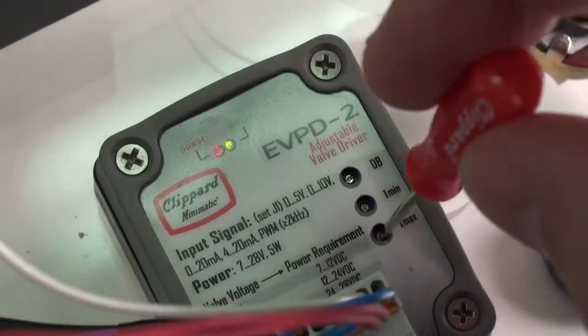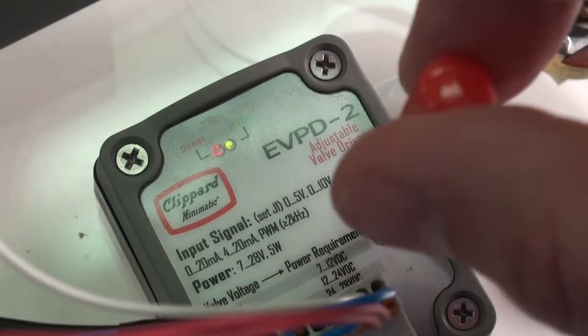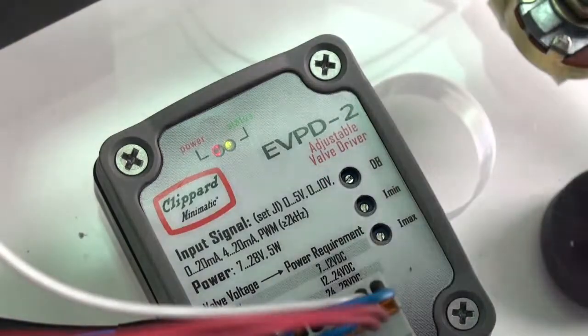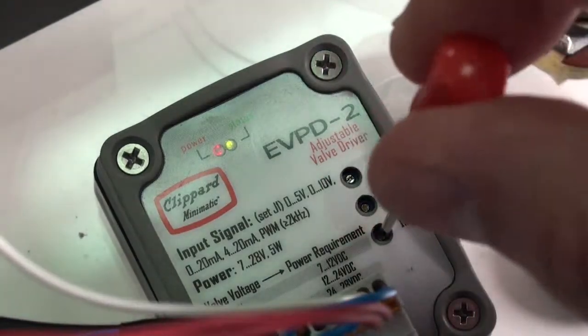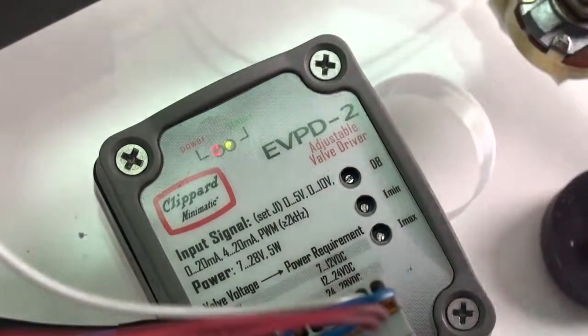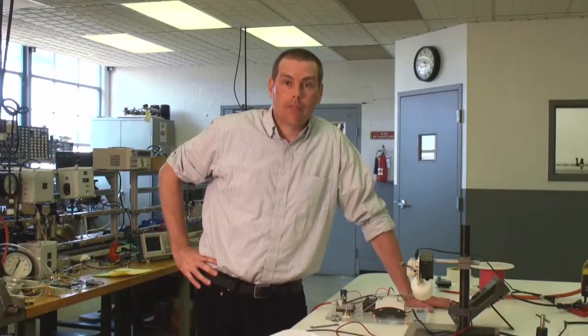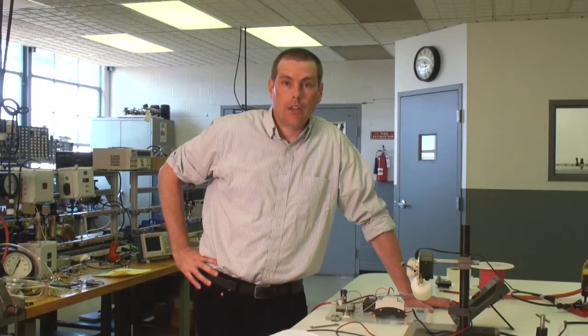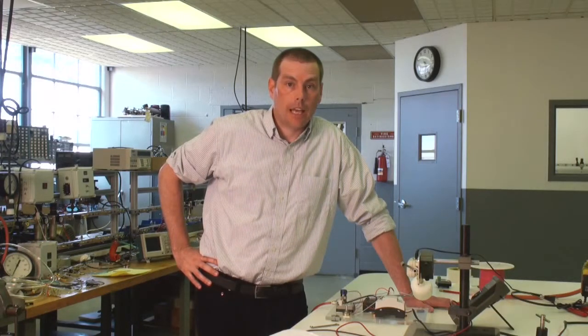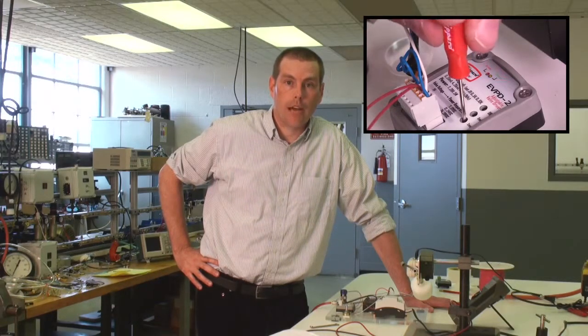Finally, we need to adjust the maximum current. For most applications, that will probably be the max rated current of the valve, and this value should never be exceeded. In some cases, you may find that the max flow of the valve is more than what you need in your application. In that case, you can use the I-max adjustment of the driver to limit the amount of flow through the valve.